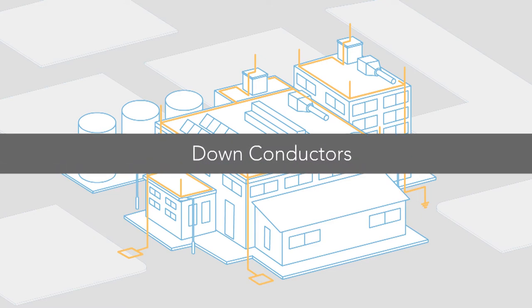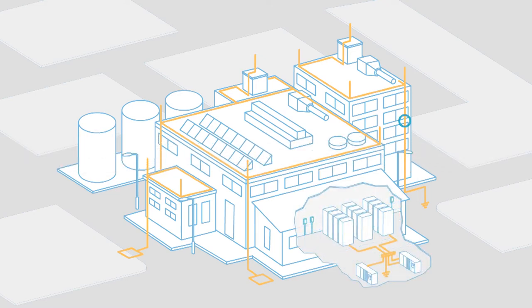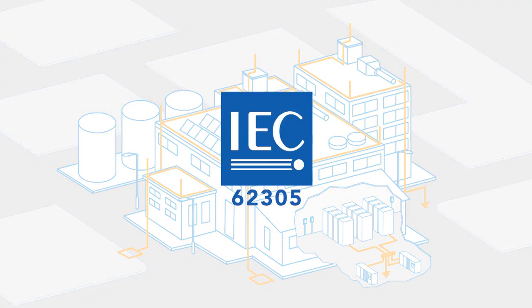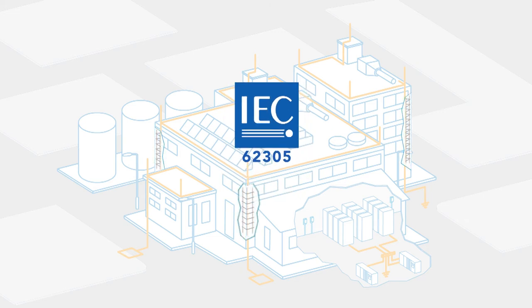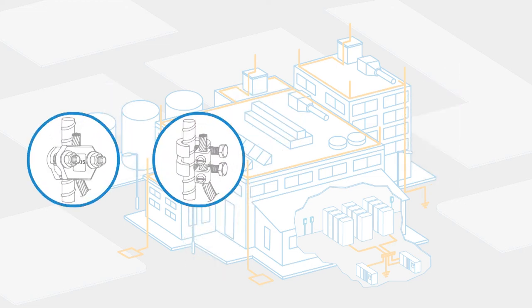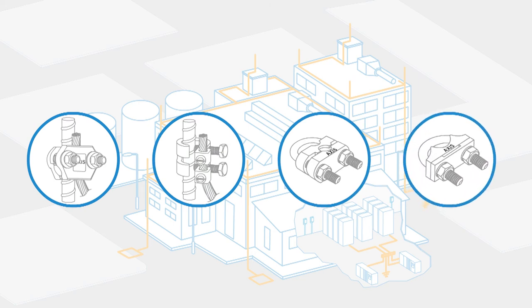Down Conductors: Down conductors connected to the air termination system with suitable Axis products should take the most direct route down the structure, with spacing between each one defined by the class of LPS. Since IEC 62305 also allows the use of rebars inside concrete structures as down conductors under certain conditions, Axis offers specially designed products to use this technology effectively.